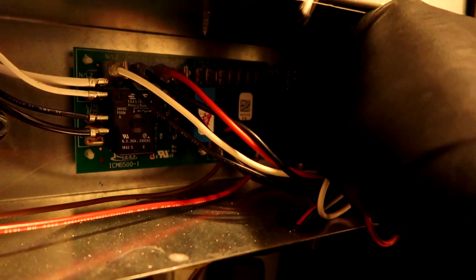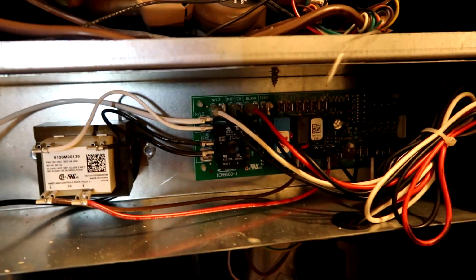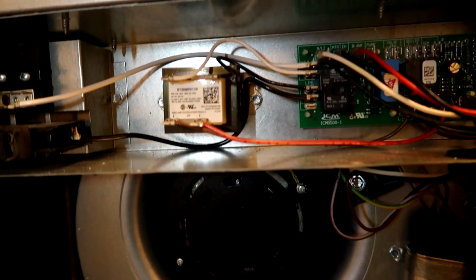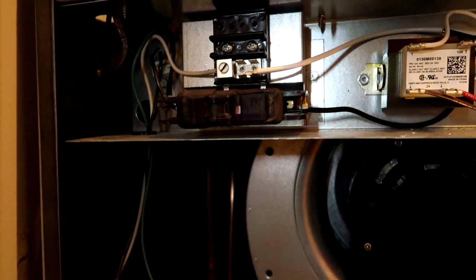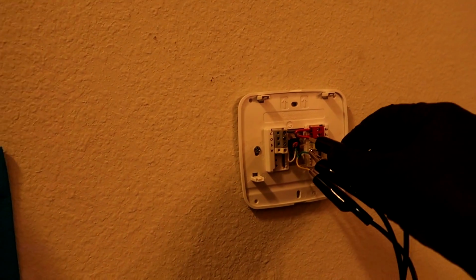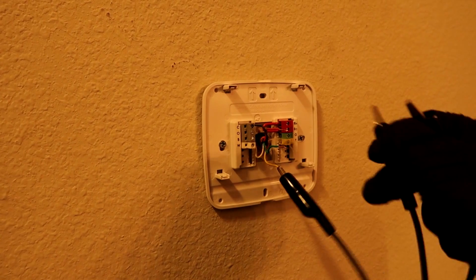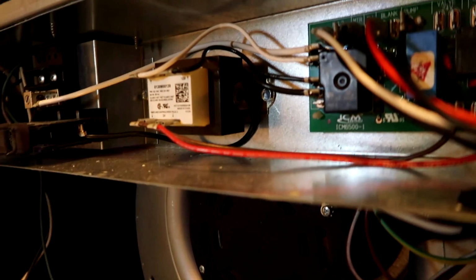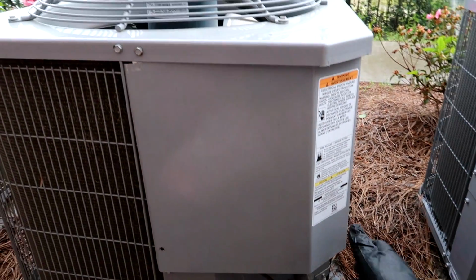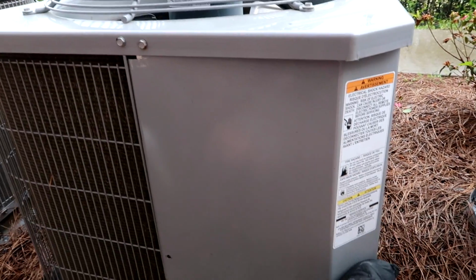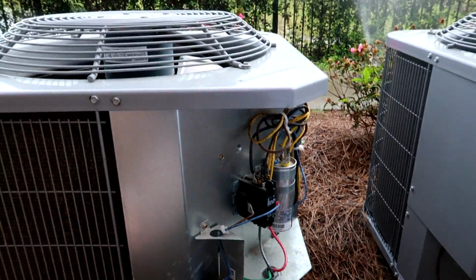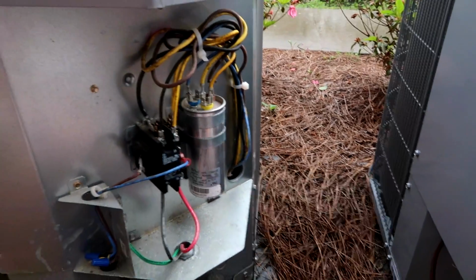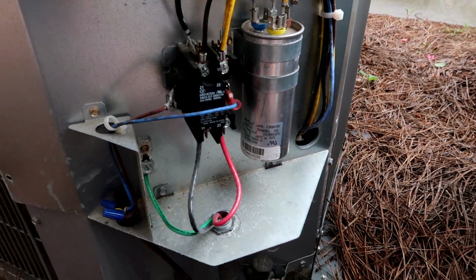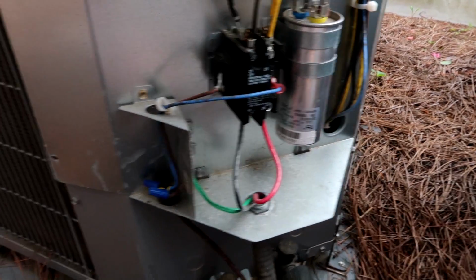Wow. Let me go outside and check the contactor before we go any further. This is really weird. I went outside to see if the condenser was on and it wasn't. And I came in, I said, whoa, something smells like it's cooking. And that transformer is really hot. Well, there was no issue until I introduced the yellow wire into the mix. That's when I started smelling the burning. When I had just green and red, the fan came on, no issues.